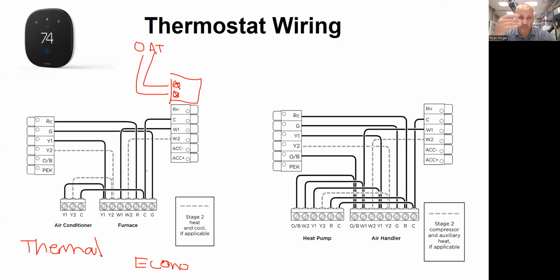To give it that changeover point, some thermostats also have the ability to learn how long it's been taking to heat and cool your structure. And you can give it a range. Say, hey, above this temperature, lock the furnace out so it can't run. And below this temperature, lock the heat pump out so it can't run. But in between these two numbers, I'm going to let you pick. I'm going to let the thermostat figure it out based on how long it's been taking to heat and cool this building at those kinds of temperatures in the past. So ecobee can do stuff like that. So hopefully that addresses Gary's question. The answer is the thermostat determines when, based on the data you give it. The heat pump doesn't know anything at all. That's dumb.